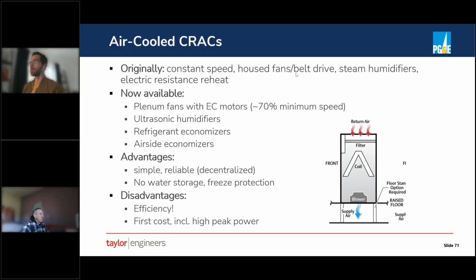The fans are more efficient. You don't have belts to deal with. EC stands for electrically commutated motors, like a variable speed drive. So now you can save fan energy at various speeds. You can get ultrasonic humidifiers, which are basically adiabatic. They're not adding heat to the system like a steam humidifier would.